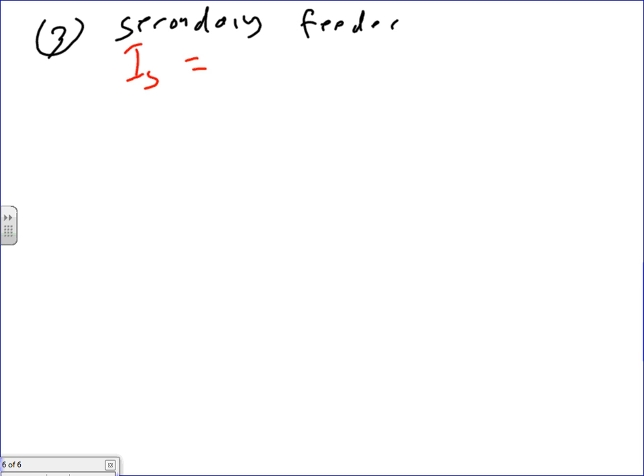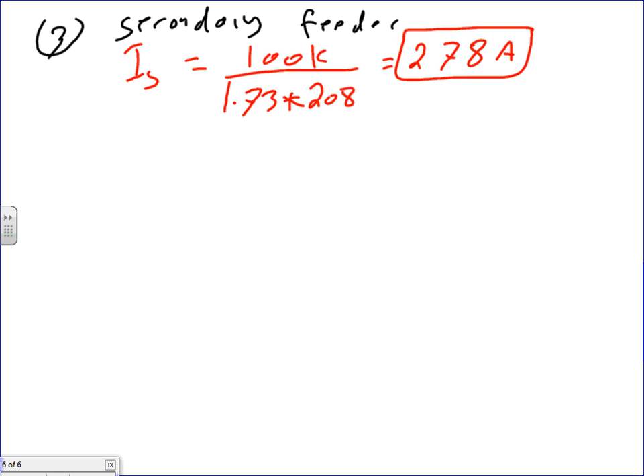So everybody knows how to find the secondary of a transformer, I hope so. That's not where the class is here, because you've done it with me before, and we've done it with Ryman. So it's 100K divided by which voltage? 1.73 times which voltage? 208. Thank you, because we're on the 208 side. And if you do this business, I came up with 278 amps. Piece of cake.